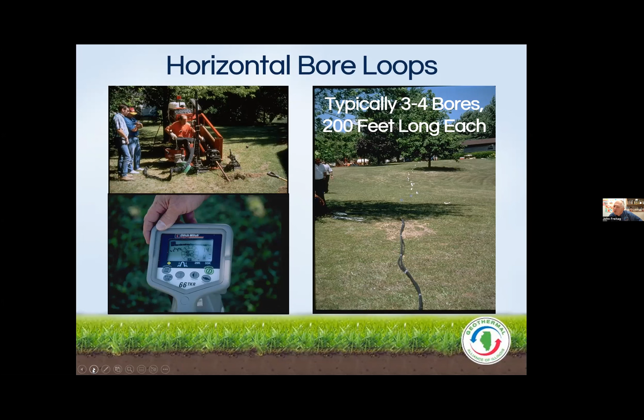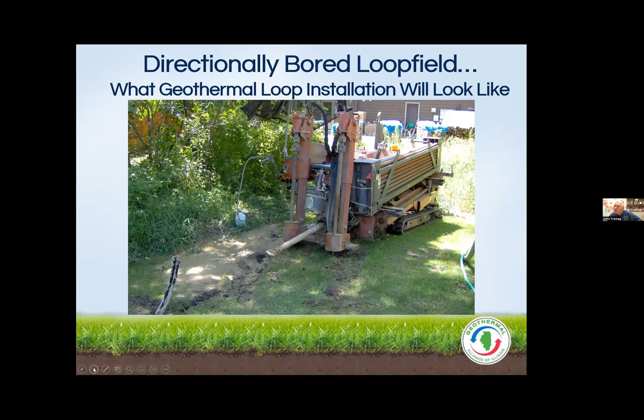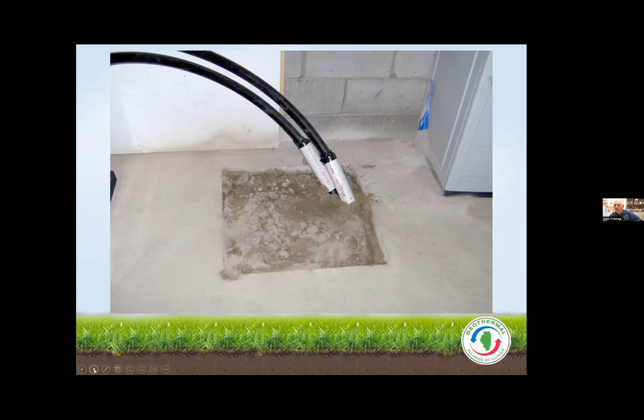This is what that type of installation might look like. You see one loop already in the ground in the lower left, and they're getting ready to bore the second loop. When they're done, that system is headered together underground, typically for residential, and the piping is brought up through a hole in the floor or wall of the home and connected to the geosystem. Remember, the picture of my system looks much like a typical furnace, except it's got two pipes connected to it, one bringing fluid in, one taking fluid back to the loop field. These systems can also be put in the ground horizontally, typically at depths of 5 to 8 feet.